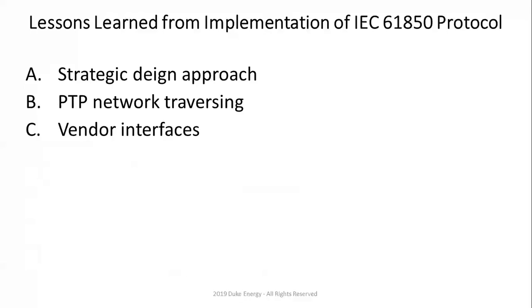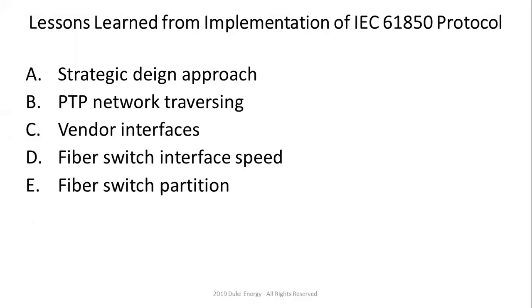So in order to simplify design, you run these fiber cables. Well, fiber cables have different speeds, right? Some of those are 100 megabits per second, and some of those are 1 gigabit per second. Some of the vendors run only 1 fiber, and some of the vendors run 2 fibers. And then you have to see how your network is going to be. So you have to make sure that you understand the requirements from each vendor, because every vendor is different. And because you have to tie everything to the fiber switch, you have to make sure that the interface speed matches whatever the speed is from the merging unit, right?